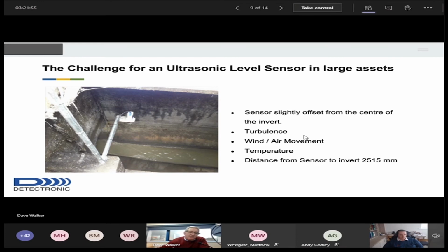Wind and air movement, not majorly a problem in sewer networks, but when you've got a very large open channel, ultrasonic sensors are used extensively for monitoring the speed of air and wind movement. And those air movement sensors are transmitting and receiving at the exact same frequency, as it so happens, as the ultrasonic level sensors we use in our sewer network. So yes, wind and air movement can have an adverse effect on the signal being received.